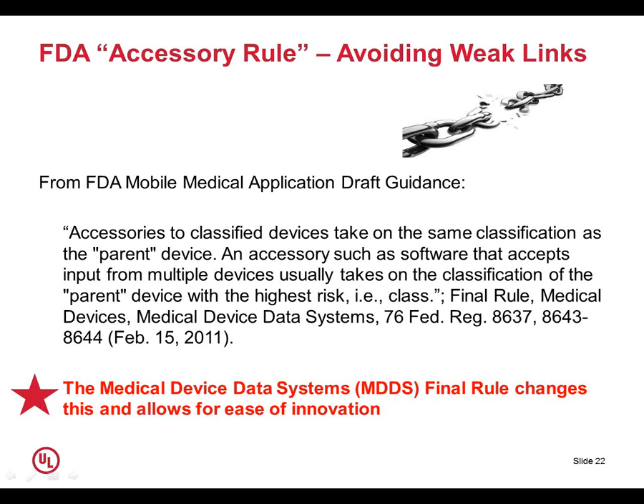From the US FDA perspective, for instance, it used to be that FDA had what was unofficially called the accessory rule. And what that stated is that if you have a high-risk device, if you connect another device to that device, then that second device takes on that same high-risk classification. So for example, class 3 for a medical device, as the parent device to which it connects. And we see now that as devices become much more integrated as parts of these complex ecosystems, that type of thinking could no longer effectively hold. And so FDA came up with what's called the Medical Device Data Systems Final Rule, which allows you to look at the differences in risk between these different devices and manage system safety relative to the risk involved in the different parts of the system.